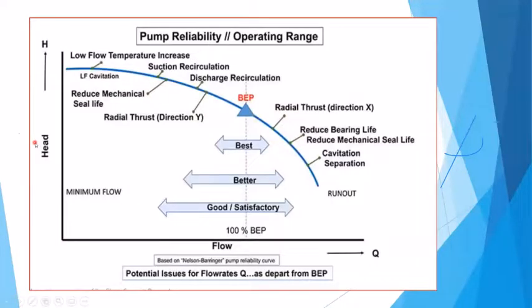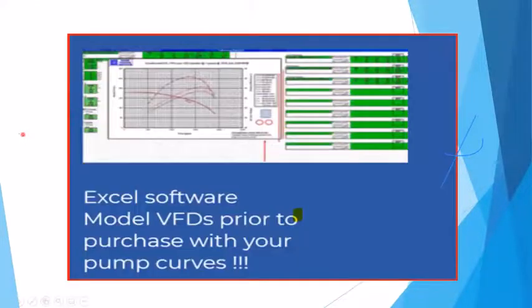And then the point is doing a good analysis on the pumps. If you're going to put a VFD in, look at those curve spots, determine where your proper efficiency loads are, and it'll end up saving you a lot of money. Also look at the actual need for total GPM over a period of time that creates the amount of acre-feet of water you need, definitely in irrigation and growth.